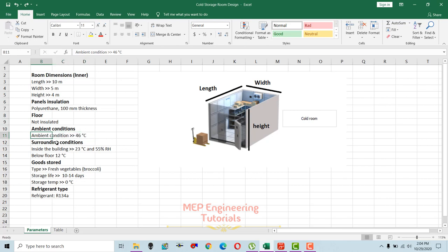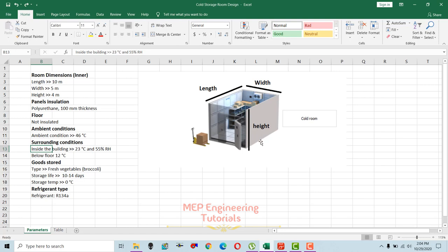The ambient condition depends on location. I'm talking about Abu Dhabi, UAE, so the ambient condition is 46 degrees Celsius — that means 115 degrees Fahrenheit. The surrounding conditions means the temperature of the spaces adjacent to this cold storage room. We keep that temperature at 22.5 to 26 degrees Celsius, so let's say 23 degrees Celsius.